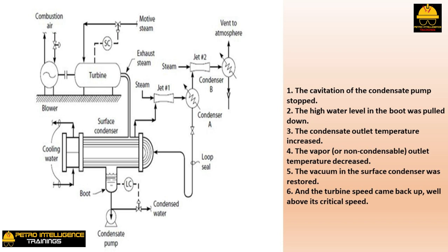After 15 minutes of operation the turbine speed slipped back down — vacuum in the surface condenser was lost again, and the vapor outlet temperature had dramatically increased. But this time the condensate outlet temperature had also increased. The surface condenser cooling water outlet temperature had increased from 100°F to 135°F — a sign of loss of cooling water flow. As none of the other water coolers in the plant had been affected, the conclusion was that the cooling water inlet to the surface condenser was partly plugged.